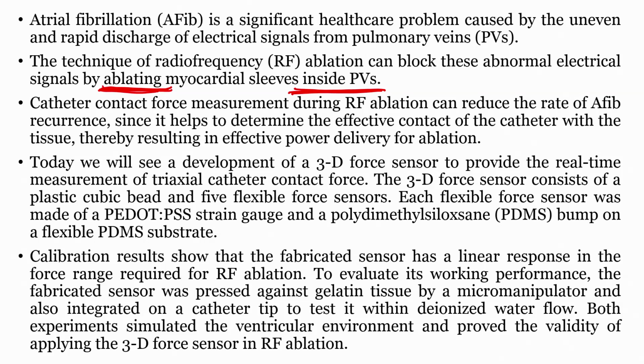Now, if this is the heart and this is the catheter, we need to understand the force that a clinician is applying during the treatment. If the force is more, then regions which do not need to be ablated will also get ablated, and if the force is less, then the recurrence rate would be higher.